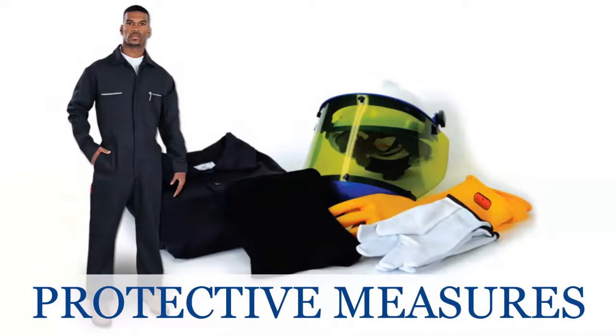For the most part—I'm not sure how familiar everyone is with the hierarchy of controls for safety—PPE is often treated as the last line of defense. I would argue in the electrical safety world that it needs to be the first line of defense, because it doesn't matter what job you're going into. Even if you're going to de-energize the system, you cannot know for sure that system's de-energized until you've tested for absence of voltage.